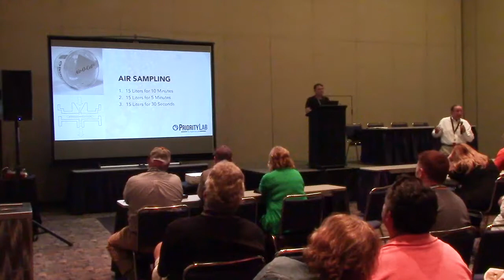That's the way to stay out of trouble. And you can go 15 liters a minute for 5 minutes if you got high debris. I don't recommend it because it's almost never too high of debris. 10 minutes. The aerosols that we sell are rated for 10 minutes at 15 liters a minute. And in-wall samples are the short cycles, the 30 seconds samples. Those are in-wall cavity samples.